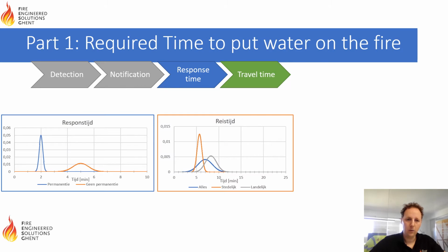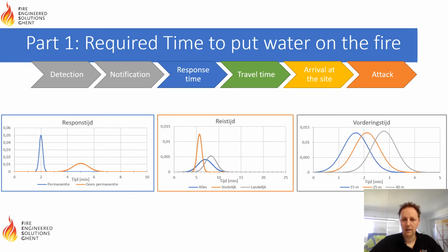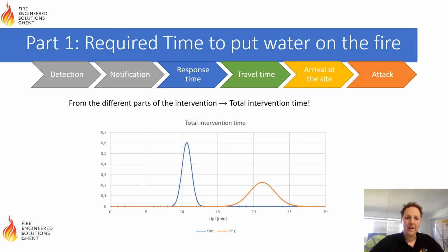Now, the way this has been set up is that basically for each of these times you have certain distributions. So the response time in Belgium is depending if it's a professional fire brigade or if it's volunteer firefighters. The travel time, obviously, depending on the distance from the fire brigade till the parking, and then the attack time, walking speed based on the smoke conditions. When adding all the different parts of the intervention, you arrive to a total intervention time, which could be short in the order of 10 to 15 minutes, or could be in the order of 20 to 25 minutes, depending on the specific case of your car park.